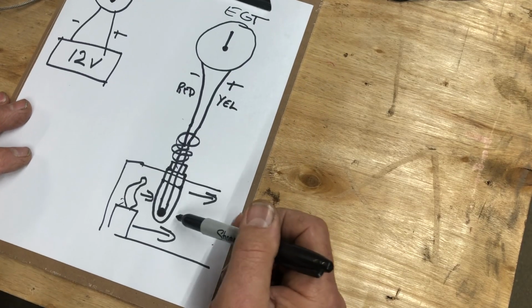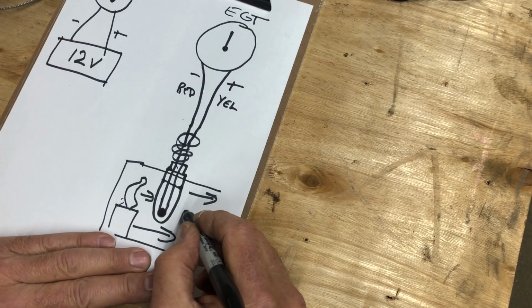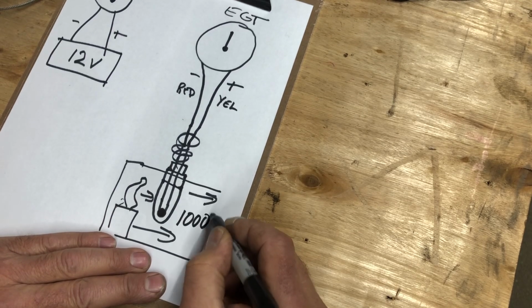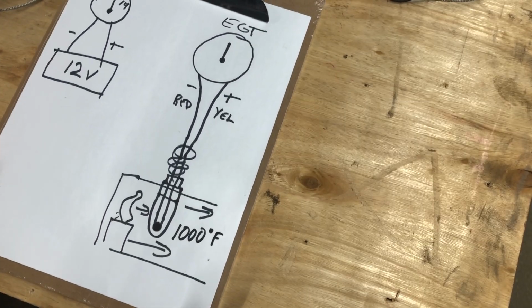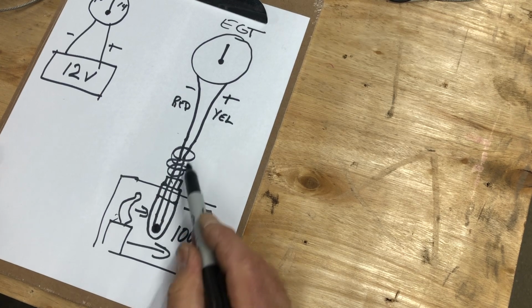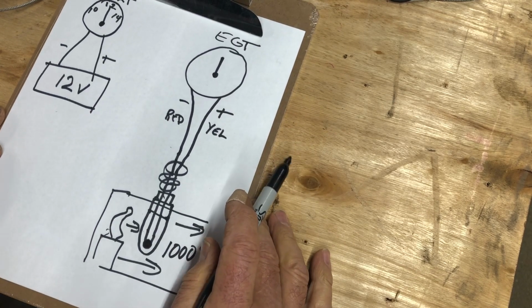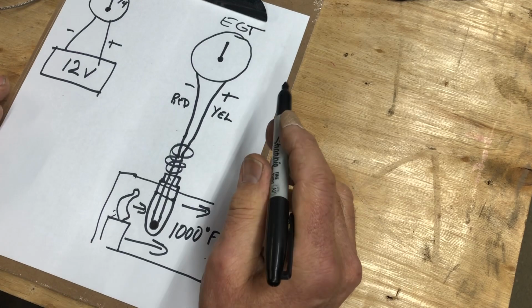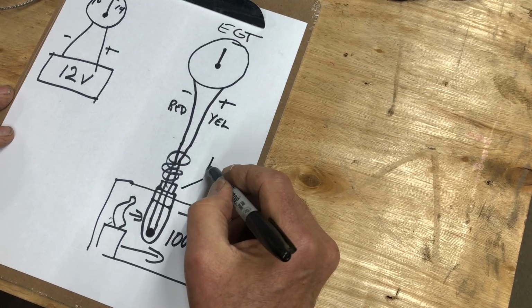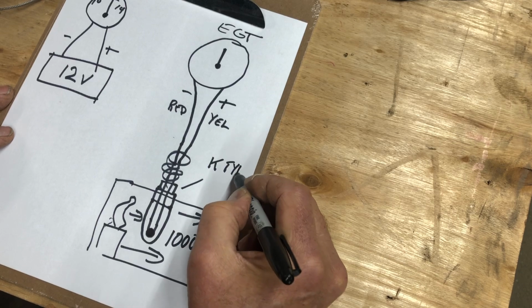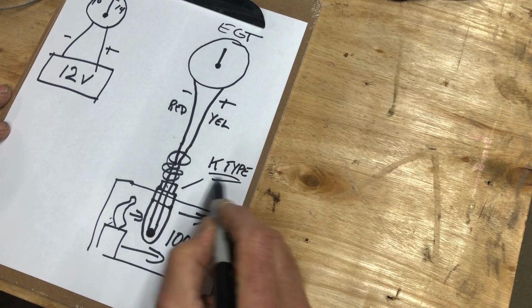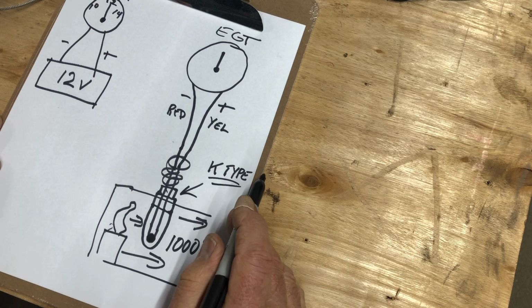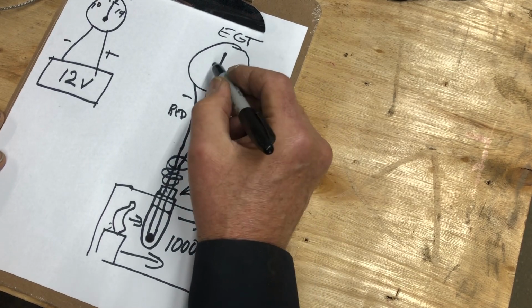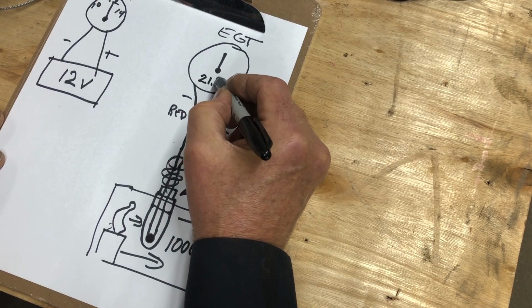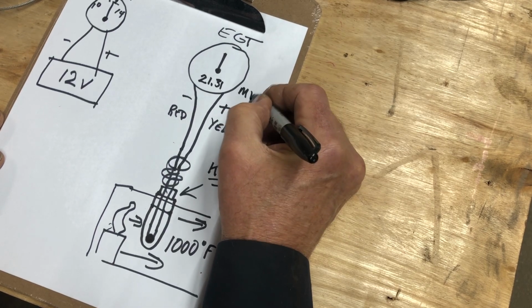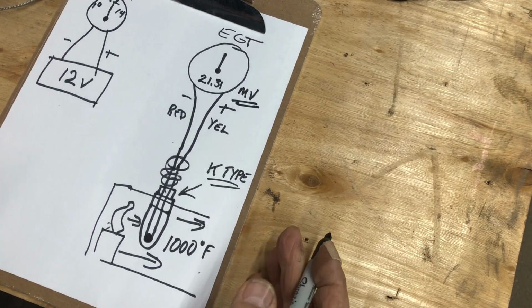So right now the engine's running and producing 1000 degrees Fahrenheit exhaust gas temperature. So how much voltage is this meter going to receive? This is for a K-type probe, so this is K-type, there are differences between probe types. The voltmeter is going to receive 21.31 millivolts. It's working in extremely low voltages.